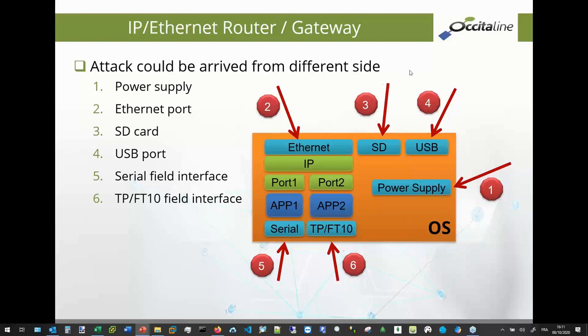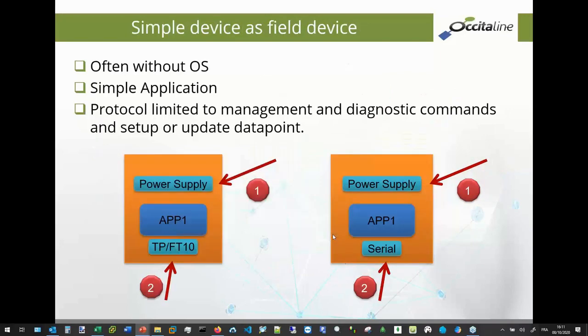On an infrastructure product or a large device, which kind of attack can you receive? First, power on or power down. The second is an attack by the Ethernet port, which we'll speak about. If you have access to the device, the SD card, the USB port, and the serial field, on the TP-FT10 channel if this is LON. This is an example for Modbus, for a specific protocol, or for MSTP from BACnet. It's exactly the same. In fact, the risk on 5 and 6 is less than on 2, and 3 and 4 can modify very easily the operating system and the functionality of the infrastructure product.